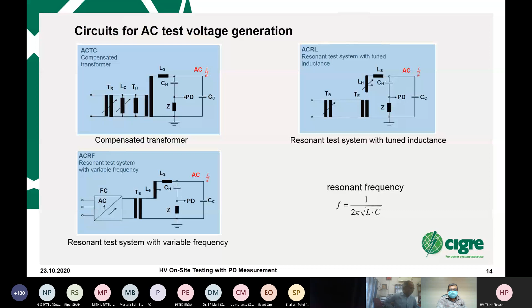Over the last 30 years, starting with GIS and from my own experience testing on site with variable frequencies, it was allowed and technically feasible, not only 0.1 hertz, but now also 30 hertz, 20 hertz or 50 hertz. The tricky part is now with power electronics, with a frequency converter. The inductance is fixed, but the capacitance can change. The GIS has different sizes of cables, and that means you have to adapt the frequency within the range allowed by the standards. In general, for cable and GIS, they have defined the frequency range from 20 to 300 hertz. So you have to change the frequency, and the big advantage is that you massively reduce the power of the in-feed you have to apply.